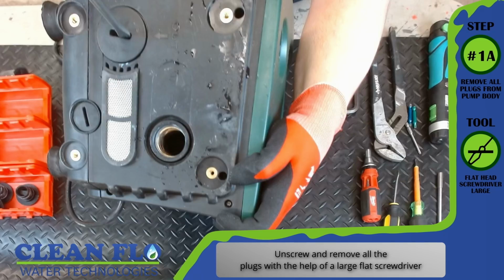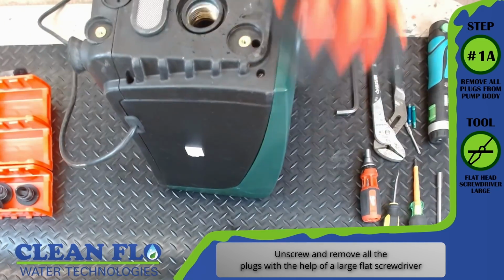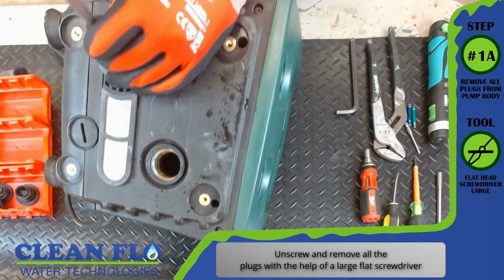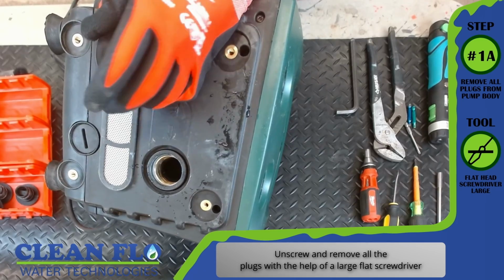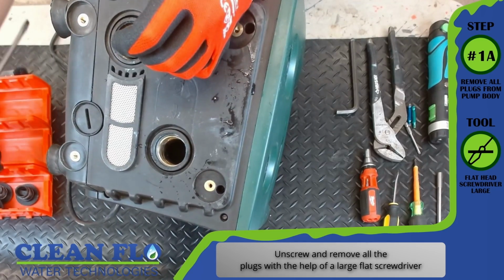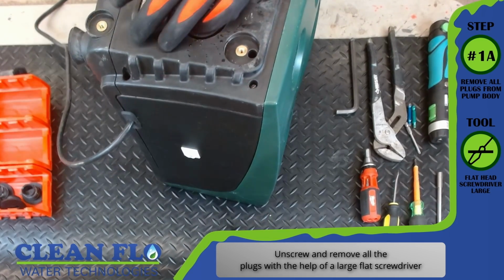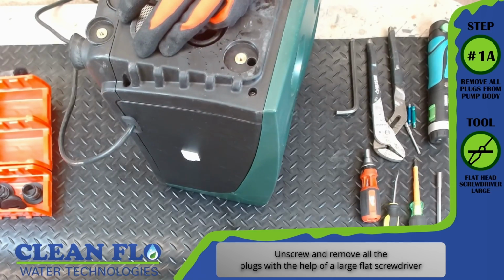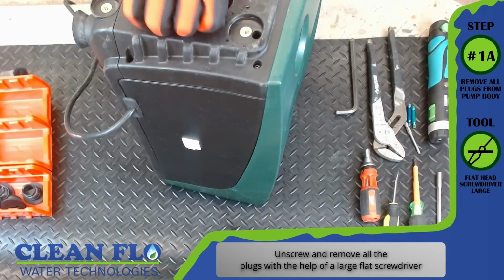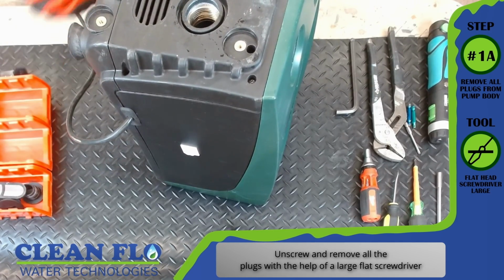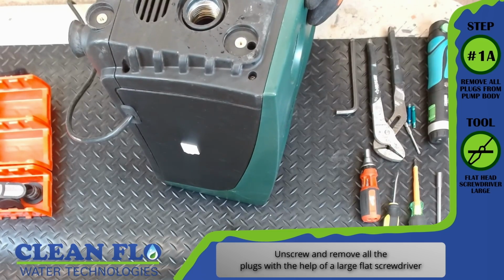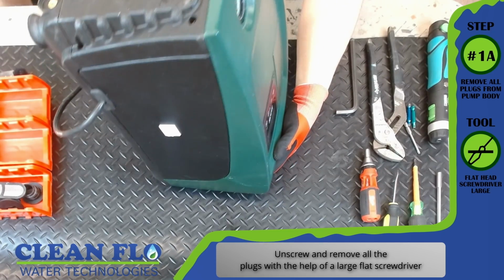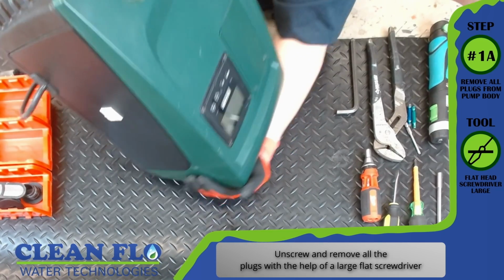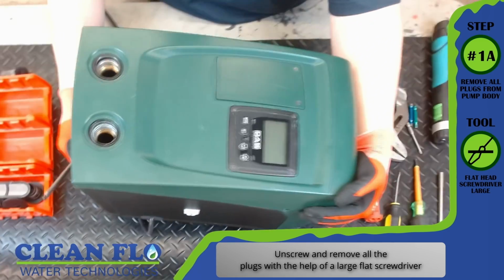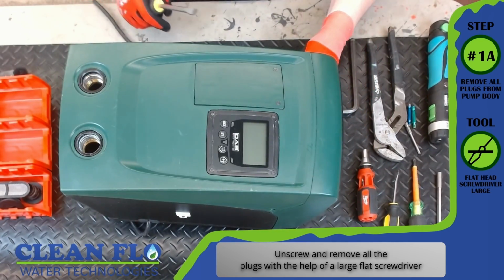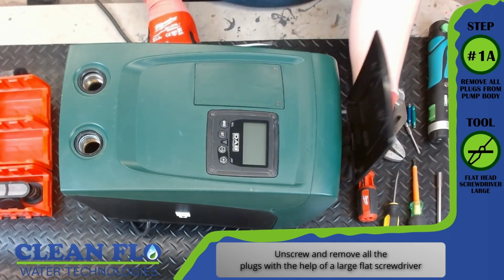The plugs are located around the pump and are sealed with an O-ring. They should not require very much effort to remove. There are two plugs on the front of the pump and 3 plugs on the bottom of the pump. I also remove the vent covering the air intake to the pump. I would take off the top cover of the E.sybox Mini 3 as well.